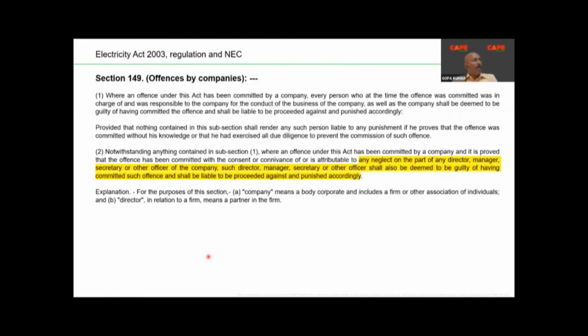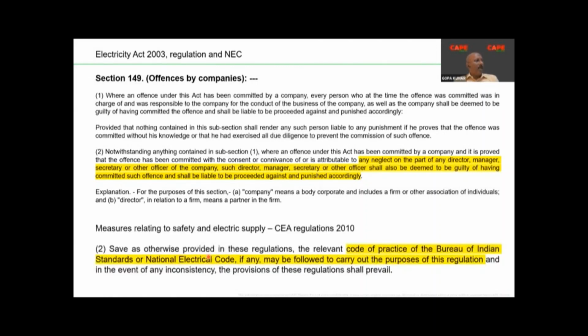Then the last one: what do the Electricity Act and rules and regulations say? Electricity Act section 149 says that in case of any accident in a premise, the owner of the building, such as the director, manager, secretary, or whatever, is actually responsible. To ensure compliance with the Act or the rules, regulations are made by the Central Electricity Authority, with measures relating to safety and electric supply. In regulation 12, sub-regulation 2, it says all the requirements of the Code of Practice of the Bureau of Indian Standards and the National Electrical Code may be followed to make a safe installation. I have not shown all the regulations, just some parts. If we go through the regulations, rules and the Electricity Act, it's very clear that in case of any accident, the owner of the building is liable.